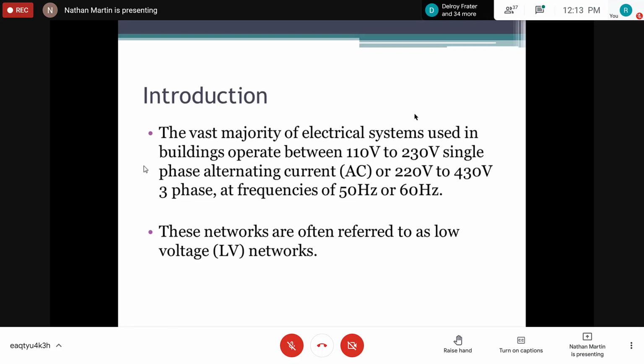If any of you have been out of the country before in a 60 cycle system, such as America, you'd realize that when you use an electrical shear that is plugged into the outlet, not a battery one, it runs silent and without noise. However, when you take that same shear and use it in our distribution network, it makes a lot of noise and doesn't clip properly. This is because of the difference in cycle, the frequency which it is designed to use. So that's a critical part you need to understand when purchasing electrical equipment.